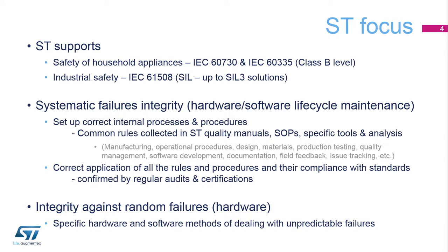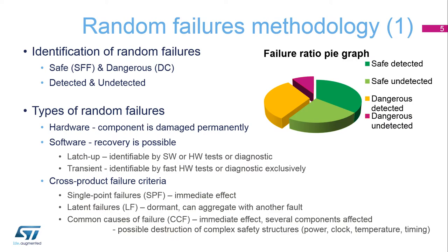To ensure integrity against random failures, specific software methods and hardware design techniques must be applied as described in the following slides. Not all random failures result in a hazardous event, and they may even be considered safe from a safety point of view. Basically, safety standards require monitoring to detect dangerous failures that may be directly or indirectly related to safety and have the potential to cause a dangerous situation. Both safe and dangerous errors can either be detected or stay hidden and undetected by the system. The more often dangerous errors are discovered and prevented in time, the more the probability of a failure propagating into a hazardous event decreases.